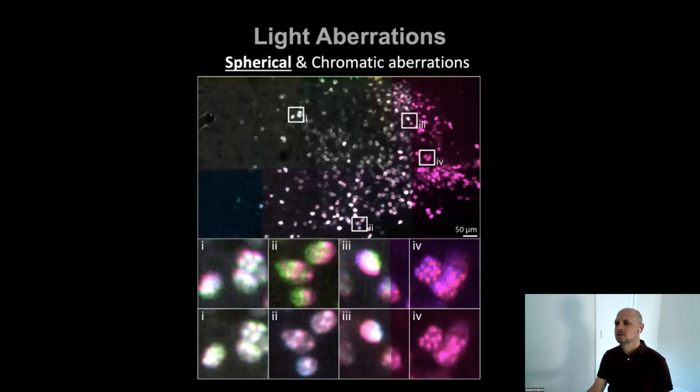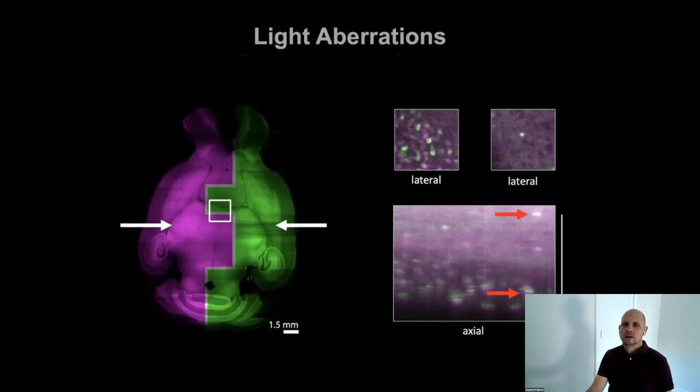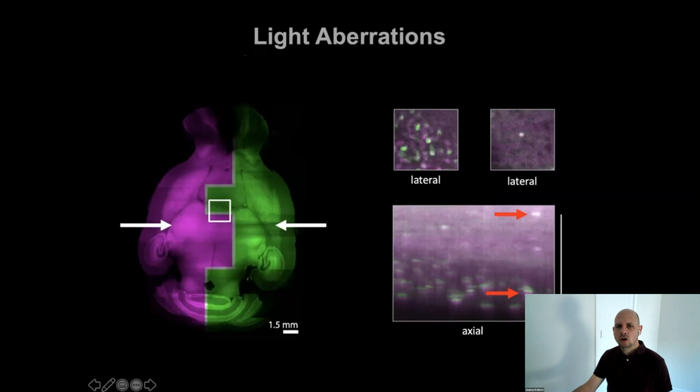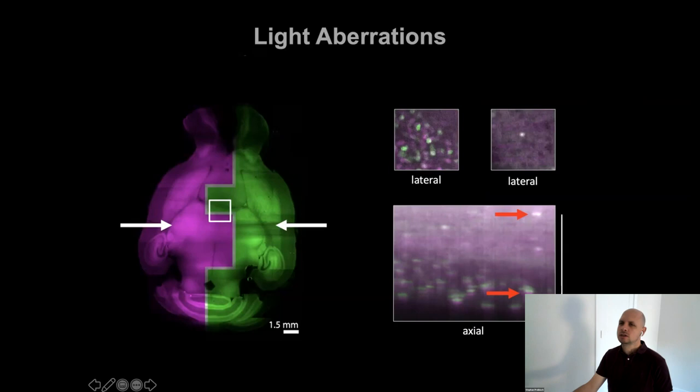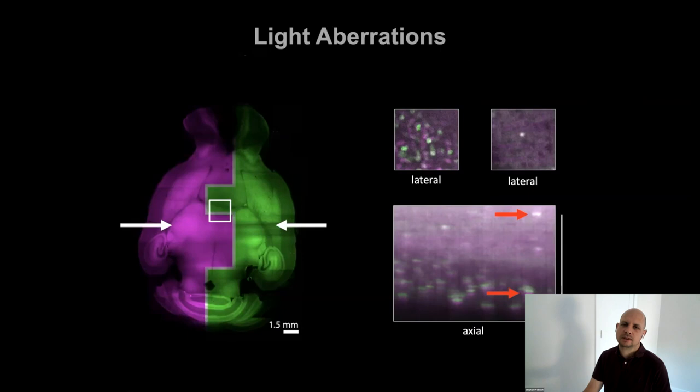Usually what happens is this is good enough to overlay the points later on. If it's not good enough, you can virtually split these images into many tiles and run this again. That usually gives you an approximation of the chromatic aberrations. You have to use this carefully - it's not the right way to do it. The right way is to actually find the models - there's some really impressive work on this, but this is often very microscope specific. So this is a tool you should use carefully, but it could improve the chromatic and spherical aberrations.